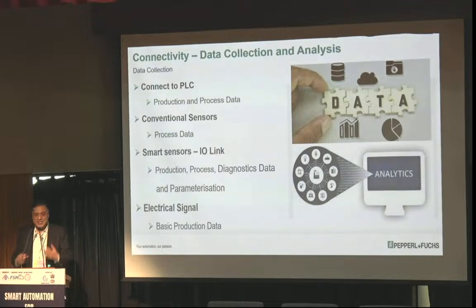So there are smart sensors which are based on IO-Link technology, which allows you to get not only the production data, the process data, plus you can do diagnostics, which will help you to do preventive maintenance, as well as parameterization. A lot of times we have seen there are machines which require a lot of parameters of the machine to be changed, because the job changes, we have to do the adjustment of the sensors accordingly. Sitting at remote locations, this is possible now.